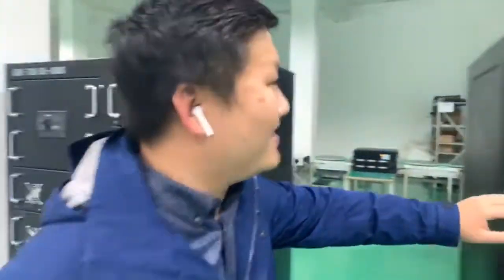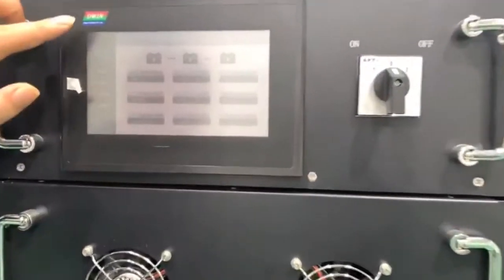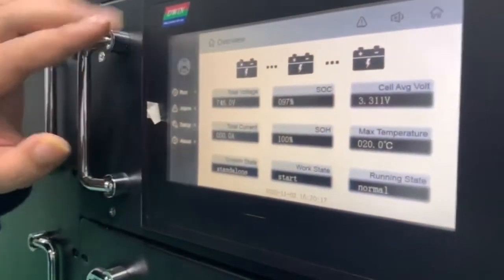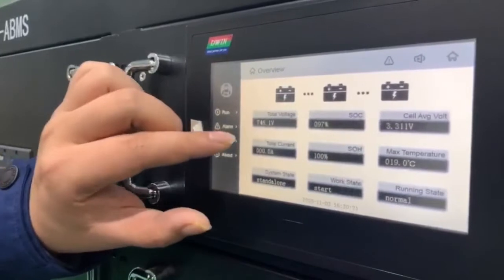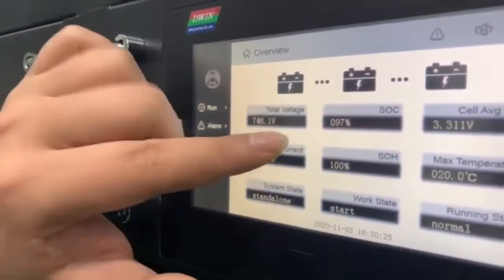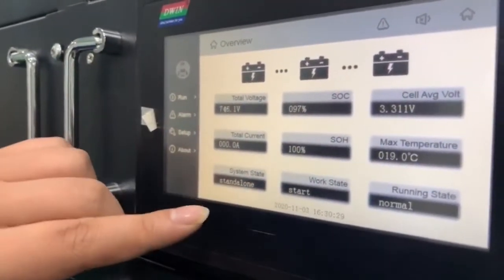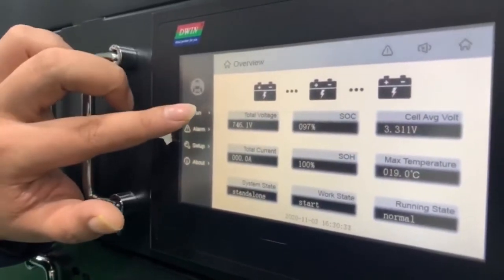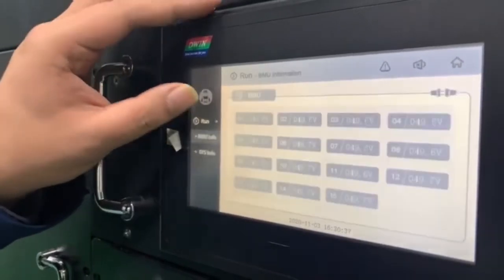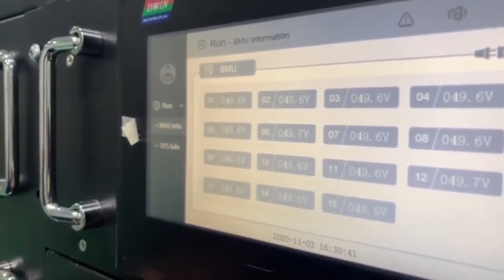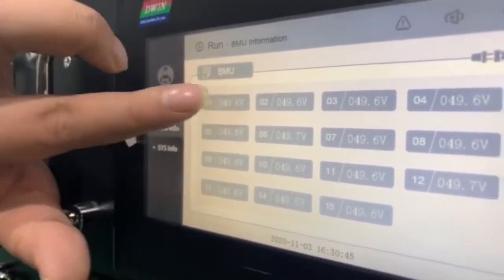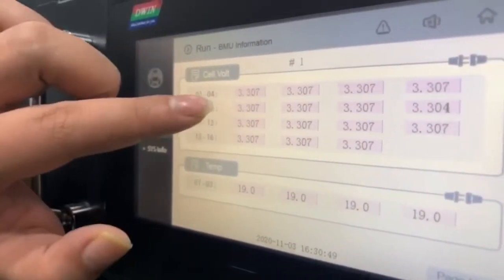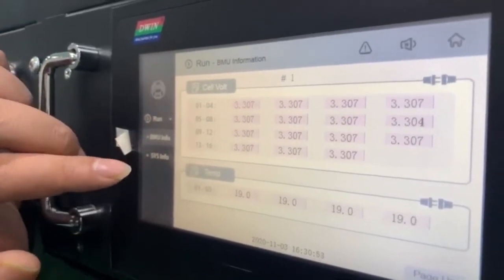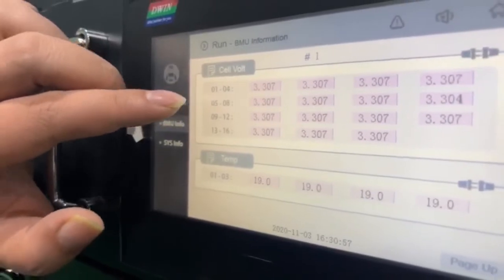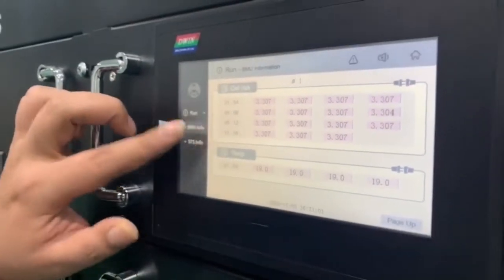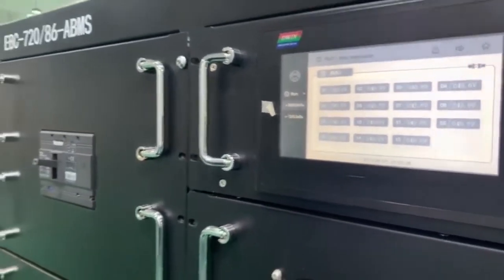I want to show you the BMS interface - this is the BMS display. On the display, we can see the total voltage of the battery system, SOC, SOH, and working state. The more interesting part is we can see the voltage and status of each battery module, and also for each cell - this is the voltage for each cell. We can see here, 3.3, which is the standard voltage for LFP battery. So the BMS system has a quite smart interface.